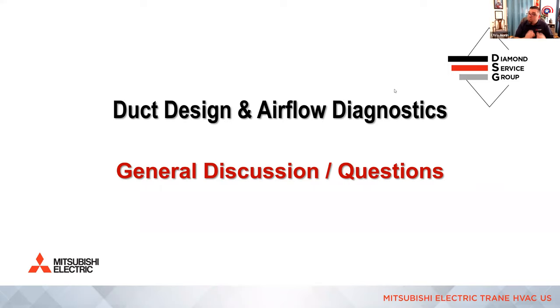Yes, if you use a heat pump thermostat and you have the capability of using that with the furnace, meaning there's more than one airflow selection for heating and cooling, then yes, you could do this. The heat pump thermostat is going to integrate. You could do that with Mitsubishi's with their integration stuff, right? So there's many manufacturers out there that provide integration controls. You're going to want to match the fan speed for the heat pump based on the capacity needs. And then when you switch over, it's obviously going to run the furnace and we're going to shut the heat pump off. We don't run a heat pump and a fossil fuel appliance at the same time.